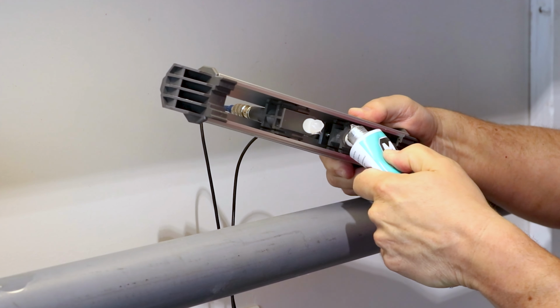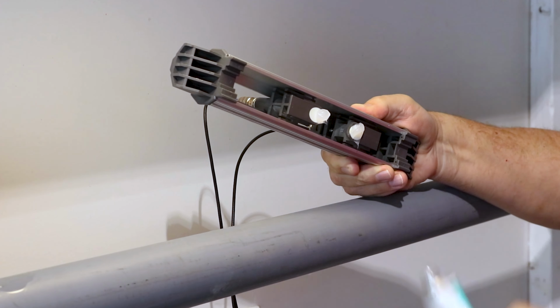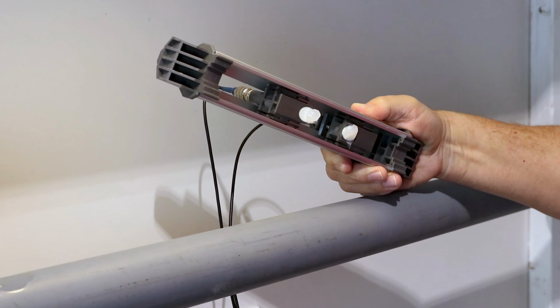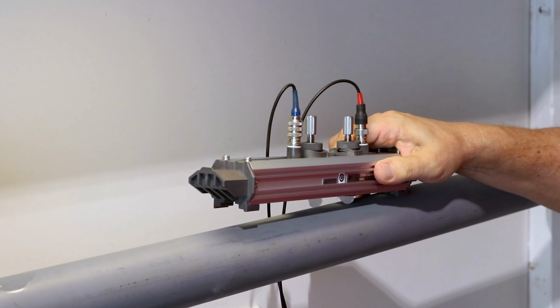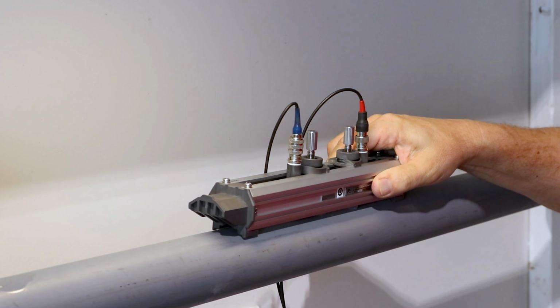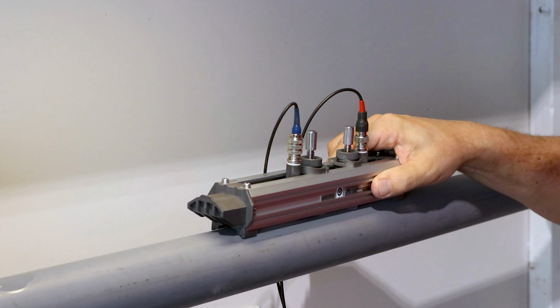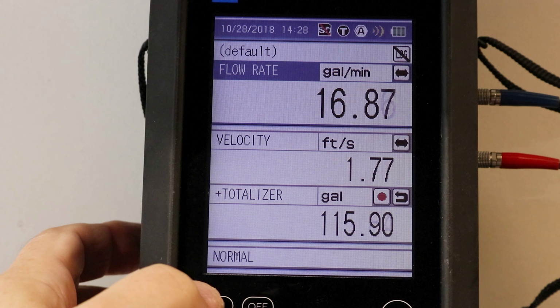One example is to use sonic grease as an acoustic couplant. You simply apply some of this grease on the face of the transducer and then handhold or strap the transducer onto the pipe, and your ultrasonic flow meter will then be able to read your flow rate. That's why we use a couplant.